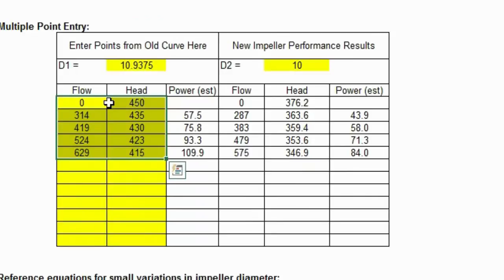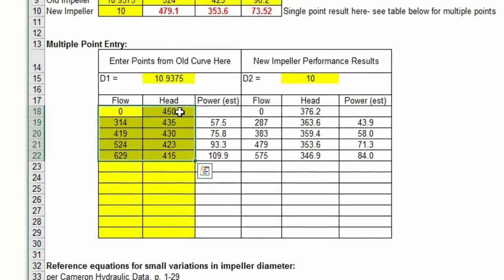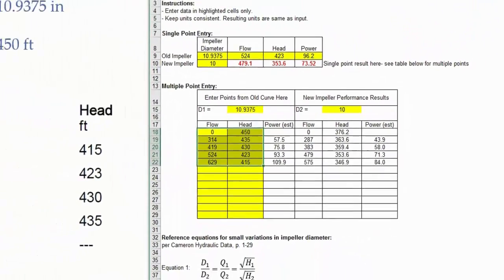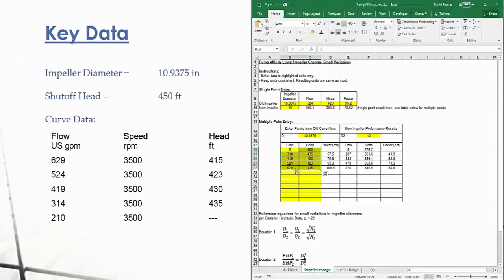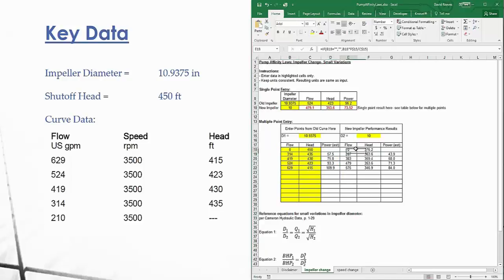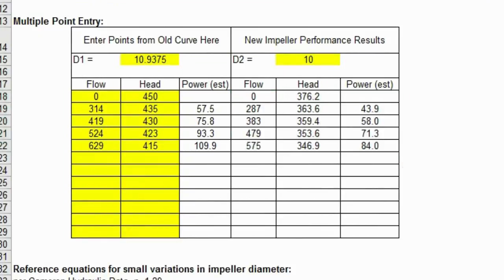450 feet is your shutoff head. There's zero gallons per minute of flow at 450 feet of head. Shutoff head means zero flow, it's shut off. And the rest of these data points, 629 through 314, are right here, and the head data points are in here as well. Once you put those data points in the table, it'll spit out an estimated power, but it'll also spit out a new curve for you here. You can see a new curve showing what that pump is going to do at a new impeller diameter. You can just change that impeller diameter to whatever you want and see the difference.